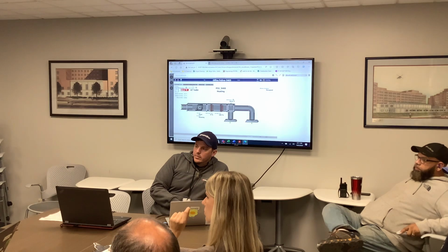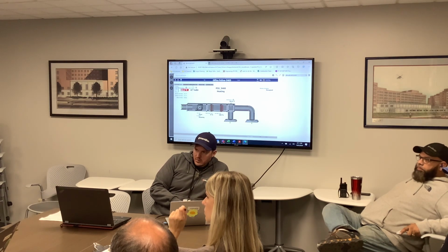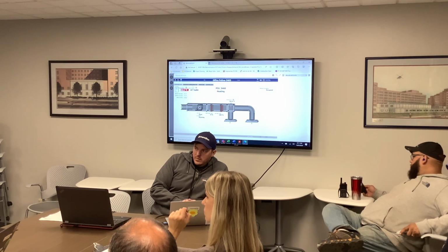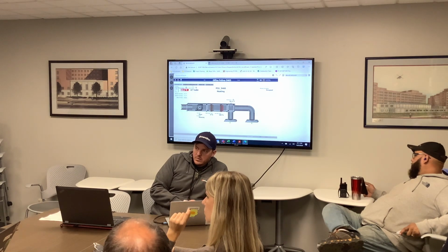Right, so like right now, when you walk in, your humidity is gonna be low due to the overnight temps. Now we go to tomorrow, what's the expected temp tomorrow, 81? Right now, you'll still be at a low temp, especially on that side of the building. You're gonna get a lot of sunlight, humidity's gonna go up, so it should be calling for reheat, I wanna say no later than 2:30. What are you gonna do then?